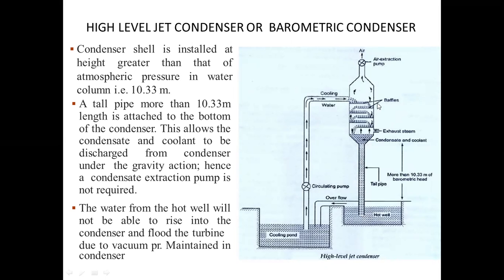So you can see the process is the same whether it is parallel flow or counter flow, right? This diagram is of counter flow where cooling water enters from the side top and exhaust steam enters from the bottom side, and there are baffle plates, they come in direct contact, and an air extraction pump is there. The condenser shell is installed at a height greater than that of atmospheric pressure in a water column, that is 10.33 meter. A tall pipe more than 10.33 meter in length is attached to the bottom of the condenser. This allows the condensate and coolant to be discharged from the condenser under gravity action. Hence, a condensate extraction pump is not required. The water from the hot well will not be able to rise into the condenser and flood the turbine due to the vacuum pressure maintained in the condenser.